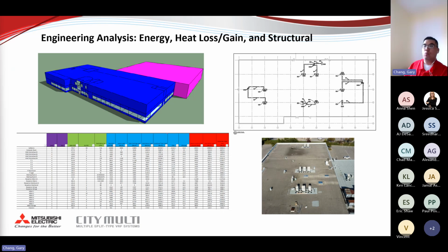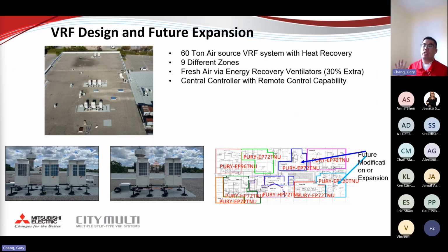So the idea is we are finally finishing it. We actually go from a 90-ton R22 rooftop unit into a 60-ton air source VRF system with heat recovery. So some of the idea, and I'll be honest, when me and my team first looked into the design, from 90-ton to 60-ton, that is quite a change, right? But it turns out, first of all, we're utilizing ERV to significantly bring down the load requirement on the ventilation side of things.